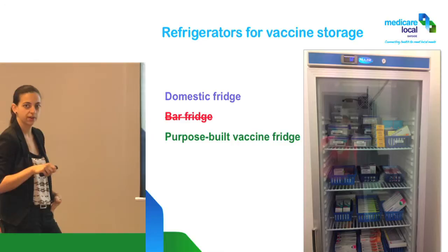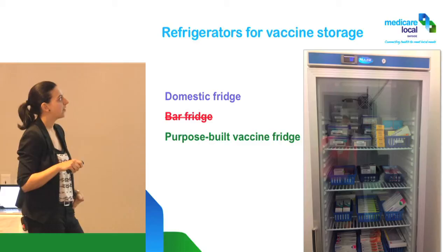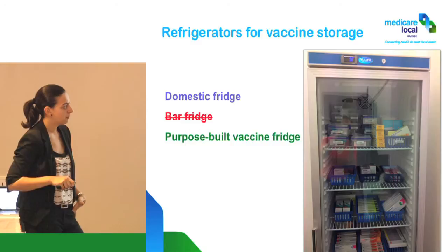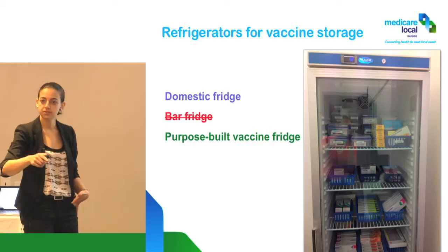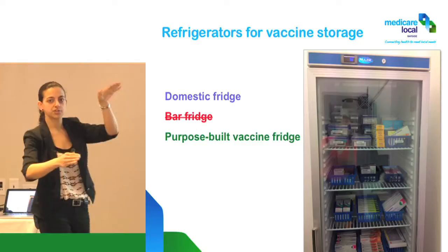The vaccine fridge thermometer is only really reading one point. You might go, oh, it's 5.8 and it's fine — but I don't know where that probe is. If this is a congested fridge, it might be 5.8 at the top but by the time you get to the bottom shelf it might actually be around 10 degrees. We need to know our fridge. We can just use thermometers at different levels, leave the door closed, and see how they're tracking. They should be within one degree of each other.